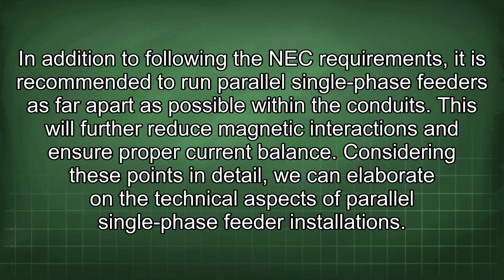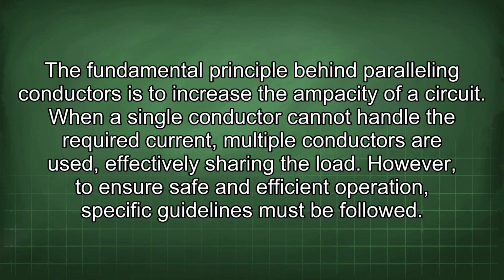Considering these points in detail, we can elaborate on the technical aspects of parallel single-phase feeder installations. The fundamental principle behind paralleling conductors is to increase the ampacity of a circuit. When a single conductor cannot handle the required current, multiple conductors are used, effectively sharing the load. However, to ensure safe and efficient operation, specific guidelines must be followed.